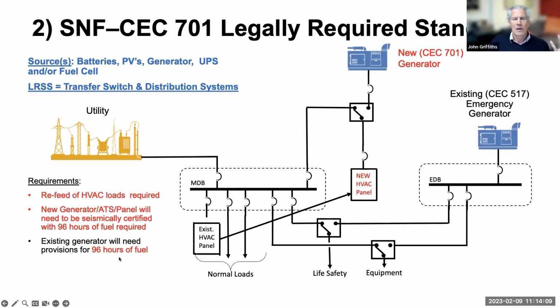And adding fuel, either on site or with a fuel service. As an electrical engineer providing advice to my clients, what would I see in this solution? Electrical - new panels, new wiring, new disruption. And if we're going to bring off 200 or 400 amps from a main panel, you need to make sure the panel has capacity. When you're connecting to this, you need a shutdown, so there's cost and disruption to your facility.